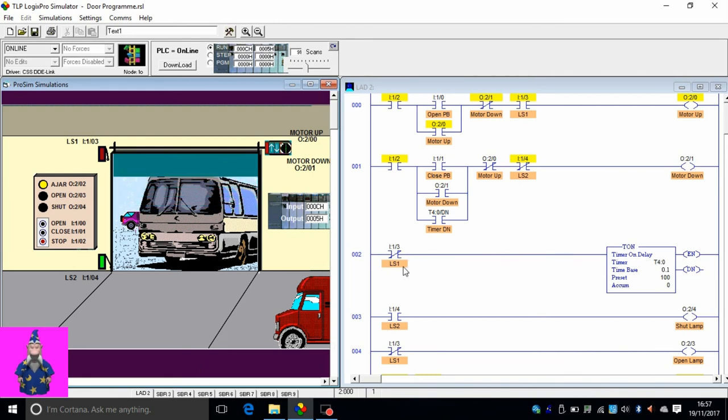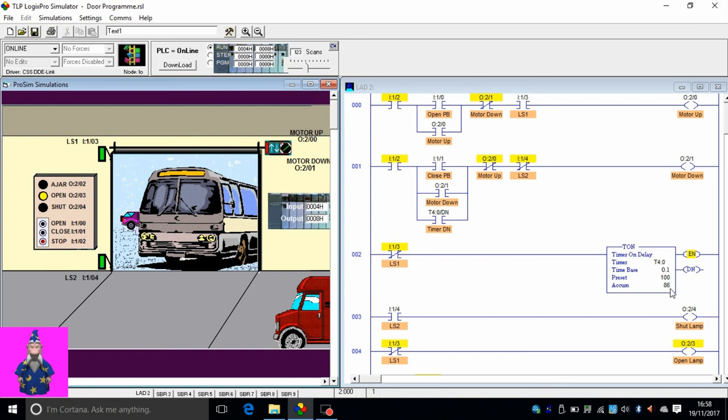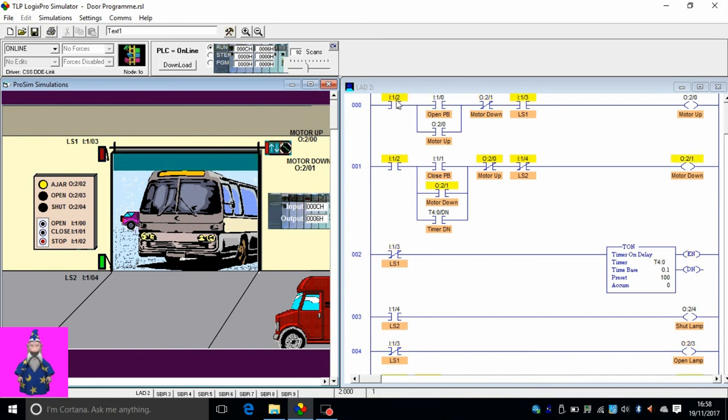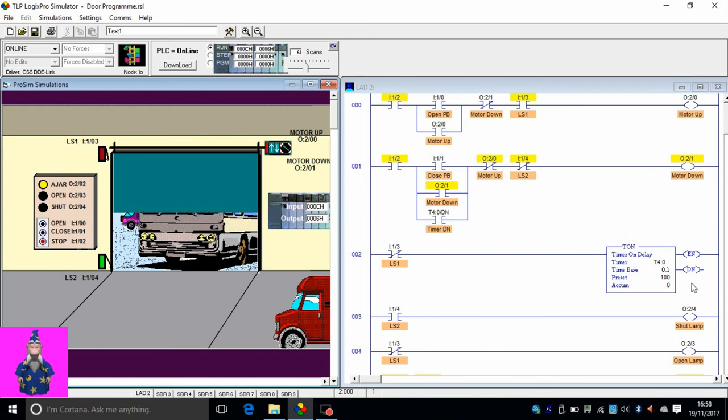Nothing is happening in this rung. As soon as it hits this limit switch, it's activated. This timer is energized, it's counting. When it gets to 100, which is 10 seconds, this will come on, done. It's activated this rung of the program. The done bit activated this rung of the program, and now the motor is going down.